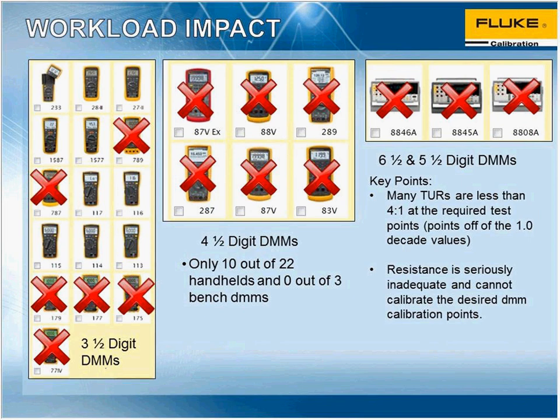As I mentioned, what would that mean? It's not so complicated. Sometimes what that means is that you might not have the accuracy to get 4-to-1 TUR or 3-to-1 TUR on some of the workload that you're trying to cover. This was just an example of one of those products on the market. We evaluated it, and what we found is that if I was a customer and I wanted to calibrate some of these products, it would be very close to the limits, and sometimes not within the limits of the 4-to-1 TUR that quality systems dictate.